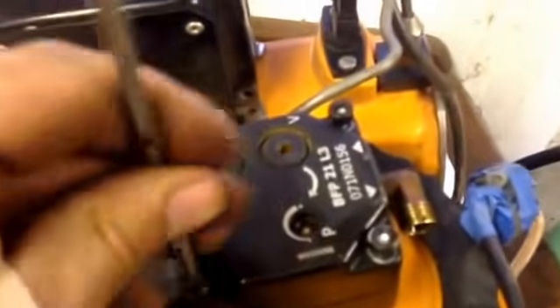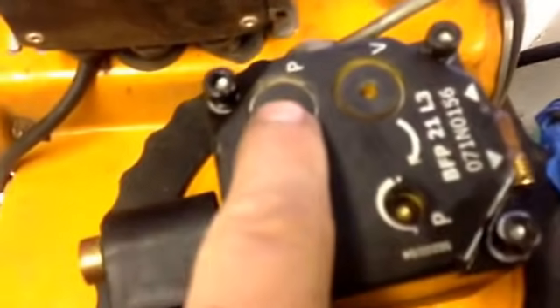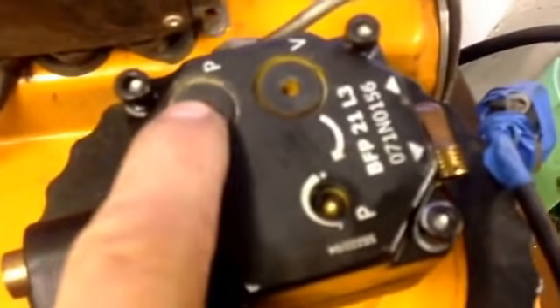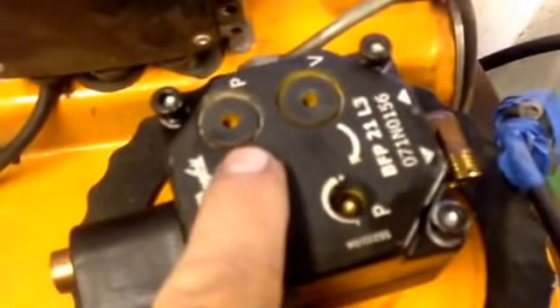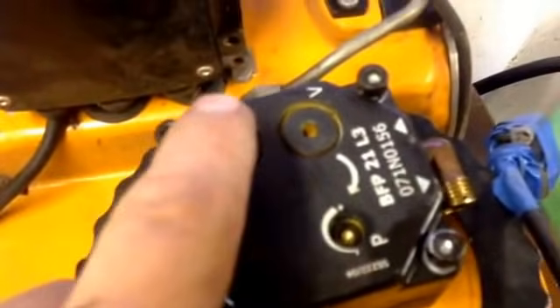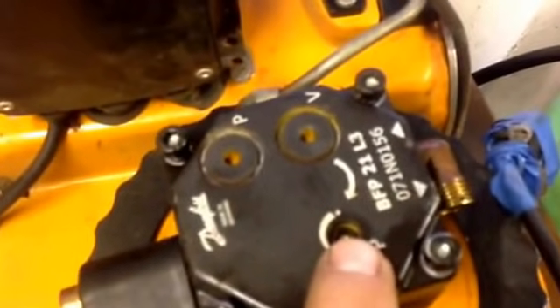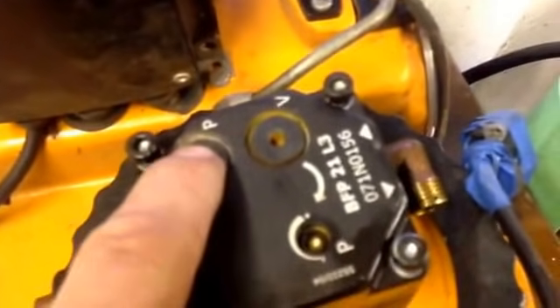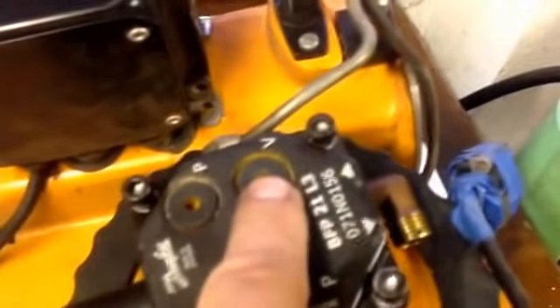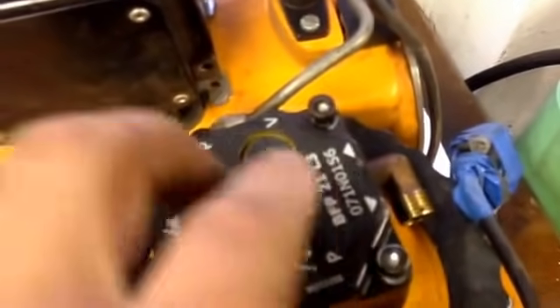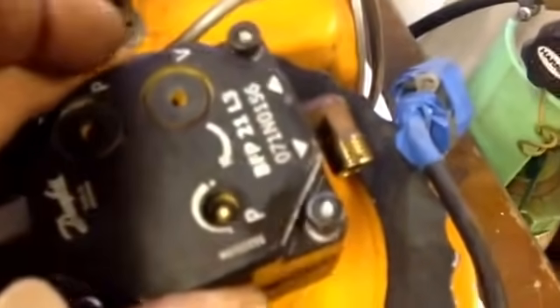If these get full of water, you can actually clear the crap out of them. Again, don't be adjusting the pressure - we'll talk about that in a bit. What you're looking to do is fix it. Take that off there - that, the P, is the pressure port. If you had a piece of test equipment, just a pressure gauge, you'd connect it to the pressure port and adjust the pressure from there. You tap into that and see what pressure it gives. And this is the vacuum port, which shows how much it's having to suck on the oil line coming to it.